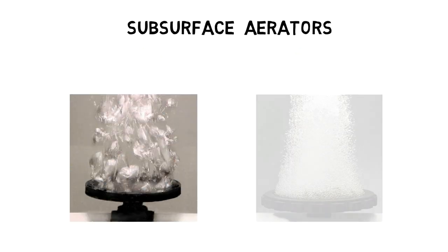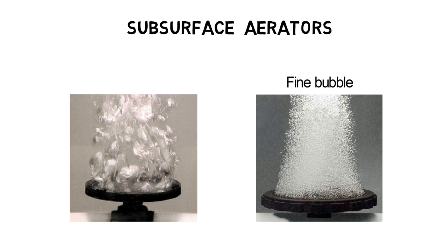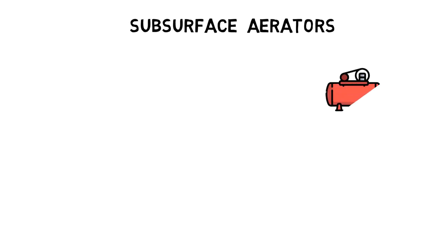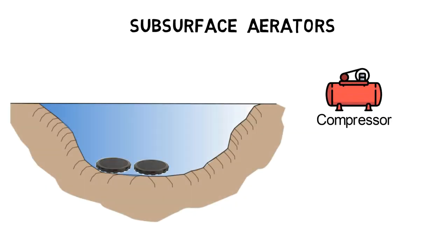Examples of subsurface aeration equipment are fine and coarse bubble diffusers. A compressor onshore pumps air through a hose which is connected to underwater bubble diffuser units. The bubble diffuser units normally have a plastic or stainless steel corpus and perforated membranes on the outside. Air which is pumped into the diffusers is released through the membranes into the water.